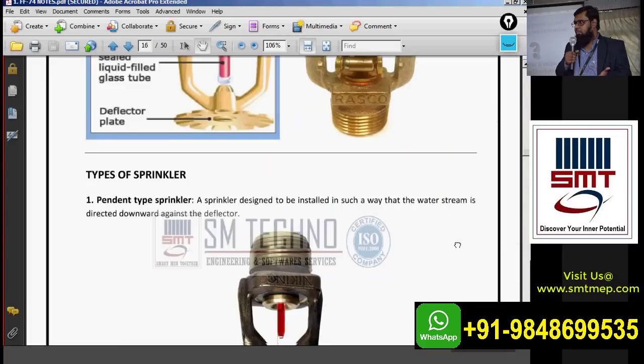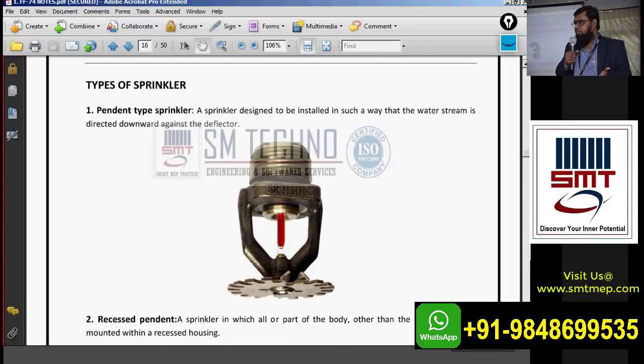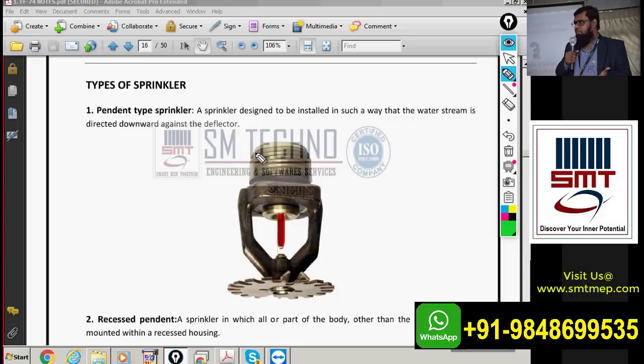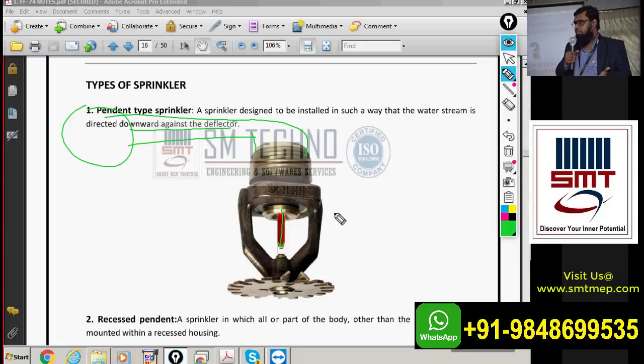Now we'll talk about the types of sprinkler. The first type is the pendant sprinkler. The branch pipe connects to the main pipe, and the sprinkler hangs down. Pendant sprinkler is used to cover the fire below the false ceiling level, or below the pipe level without false ceiling. Water is directed downwards against the deflector.